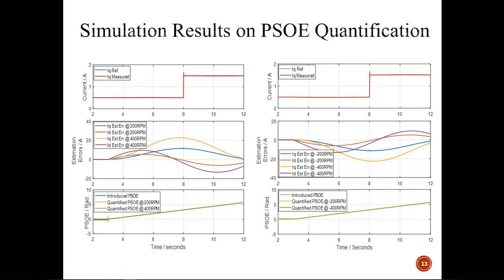For the current regulators, they assume the current is being properly regulated. However, the actual torque output is being influenced. That can be captured based on these two signals, and we are using the algorithm to compute the induced position sensor offset error shown in the bottom graph. It's tracking along with the induced error for both clockwise and counterclockwise rotation. We are assuming a linear machine model and not considering the non-linear operation range.